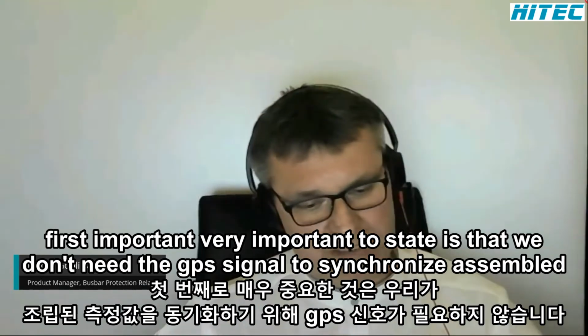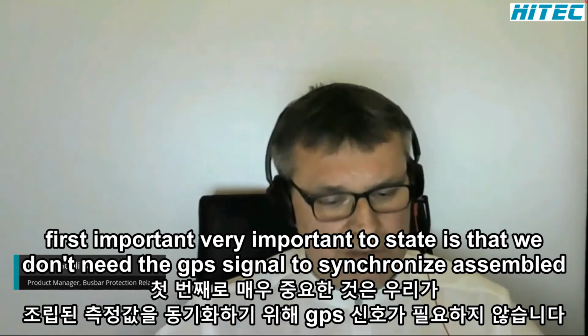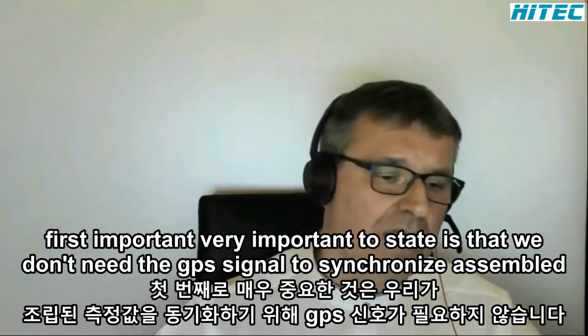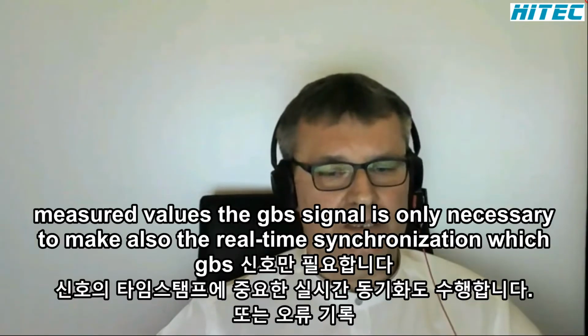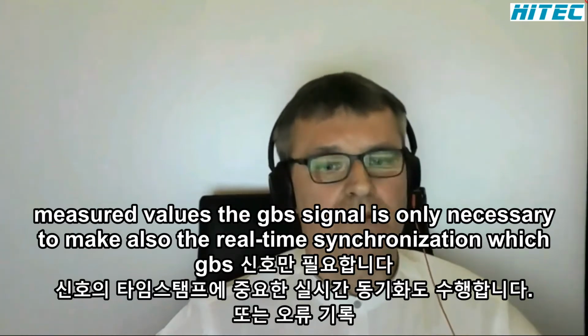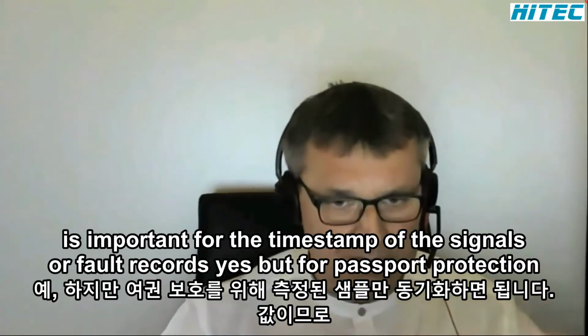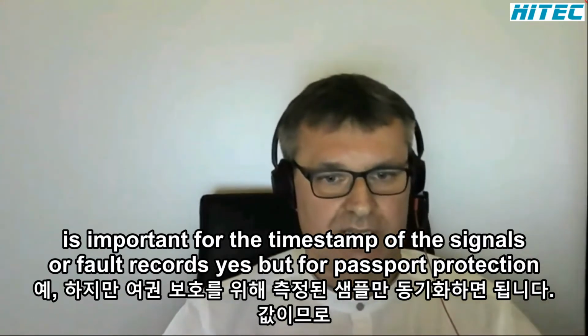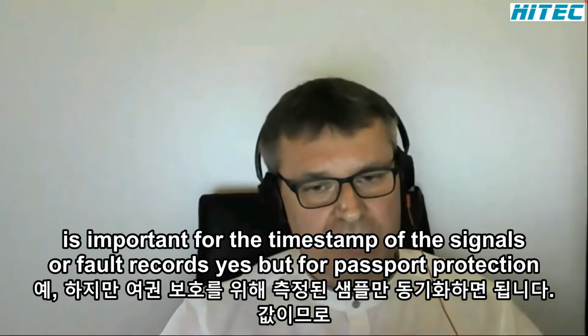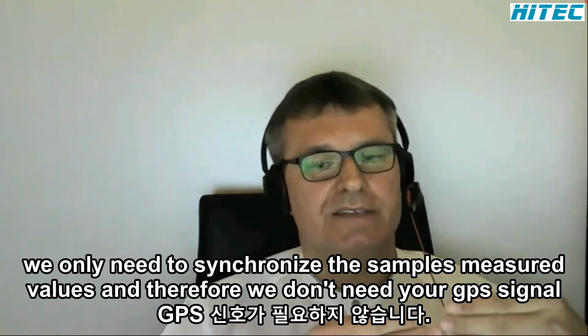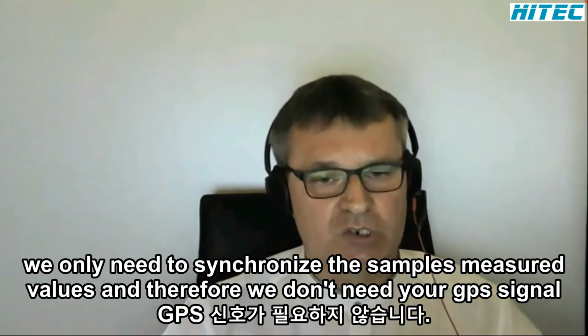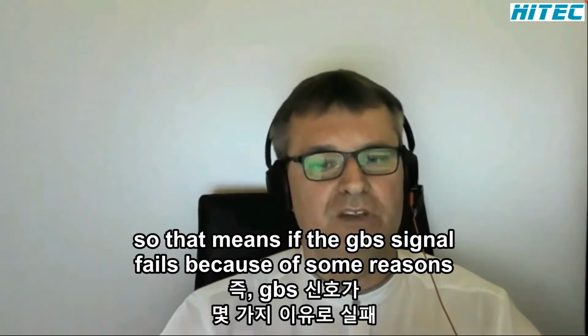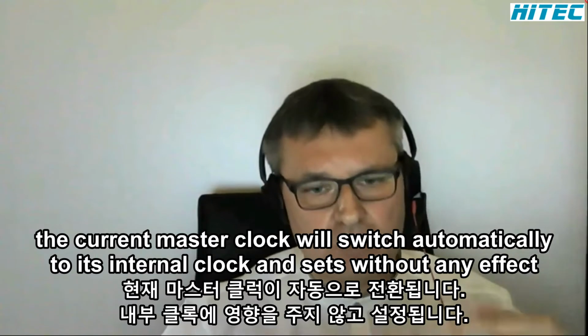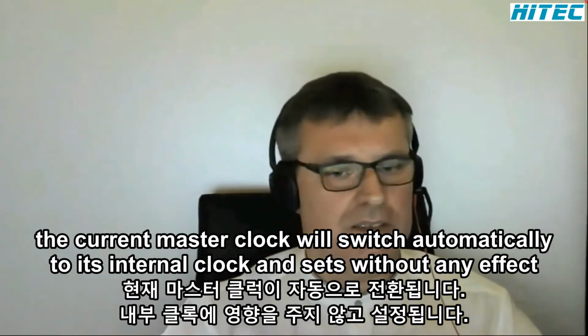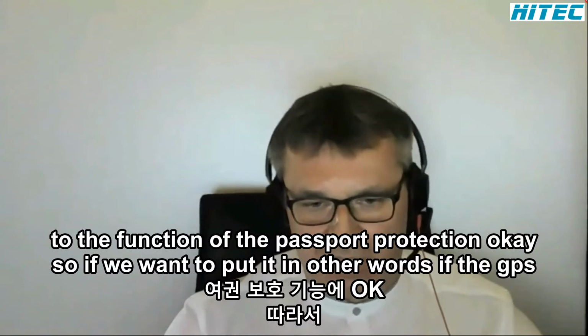First, very important to state is that we don't need the GPS signal to synchronize the sampled measured values. The GPS signal is only necessary for the real-time synchronization, which is important for the timestamp of the signals or fault records. Yes, but for busbar protection, we only need to synchronize the sampled measured values, and therefore we don't need the GPS signal. So if the GPS signal fails for some reason, the grandmaster clock will switch automatically to its internal clock, and that's without any effect on the function of the busbar protection.